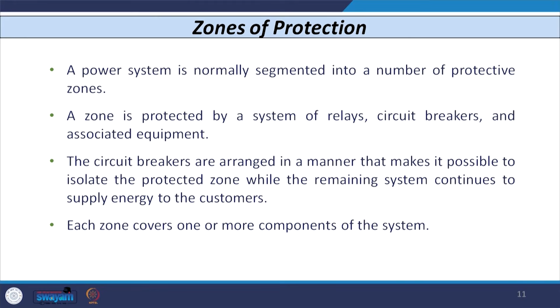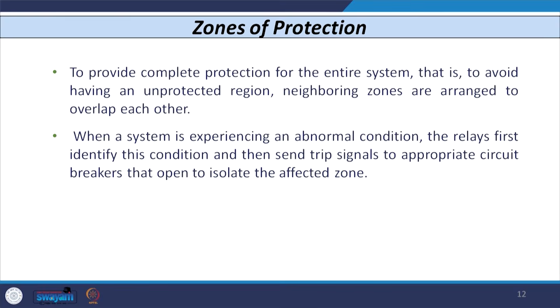Now, one more very important thing: whenever we assign a particular protection zone to a particular device or equipment, we need to keep in mind that not a single point should remain unprotected. That means if there is any region or location at which, if a fault occurs, no device is capable of sensing the fault and isolating it from the system, then there will be a blind spot. So, to avoid this, we have to overlap the zones of different equipment with other associated equipment.